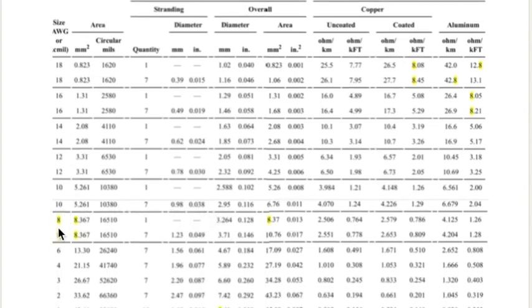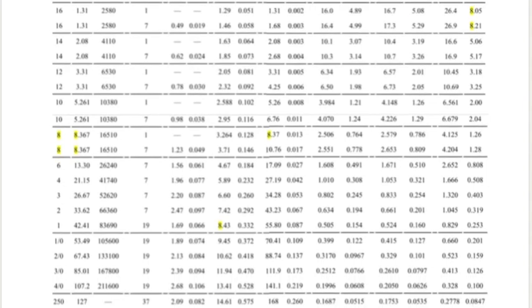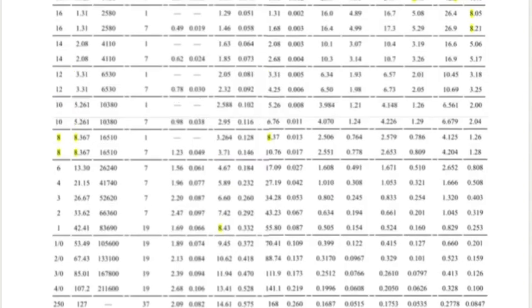The reason that it stops at 8 is that after 8, all wire must be stranded. So all this stuff from 6 down to 2,000 is all going to be stranded.